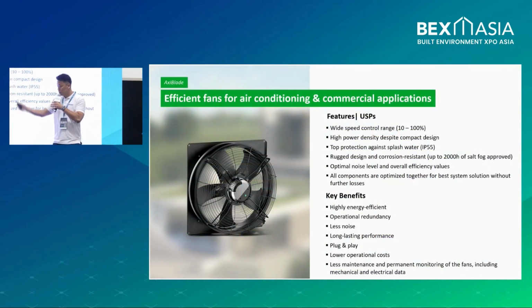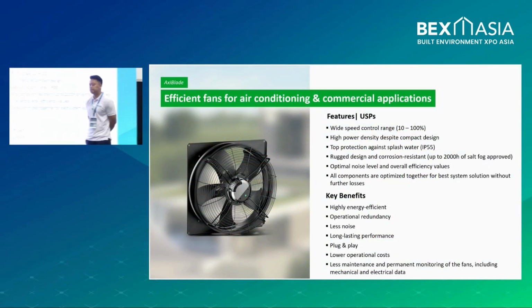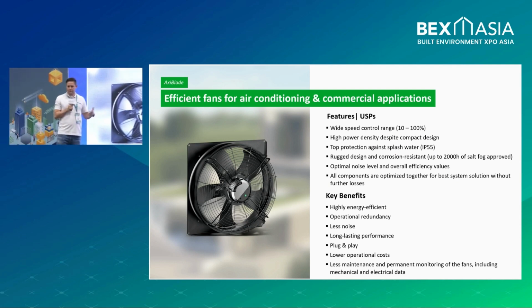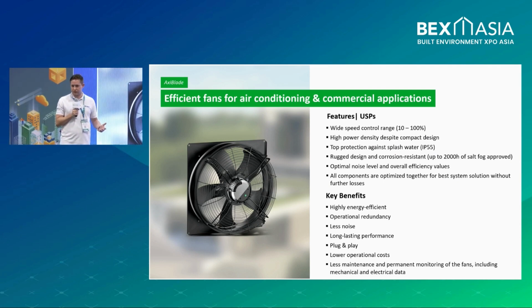Thanks, Keith. We've shown 2 examples now where we can achieve up to 50% efficiency with our EC technology solution. Looking back at the presentation Keith started with, 70% of a building's energy consumption depends on fans, cooling and air conditioning. Since we're saving 50% efficiency, when doing retrofits that means we can save 35% of the total energy cost of a building. That's a very impressive number.